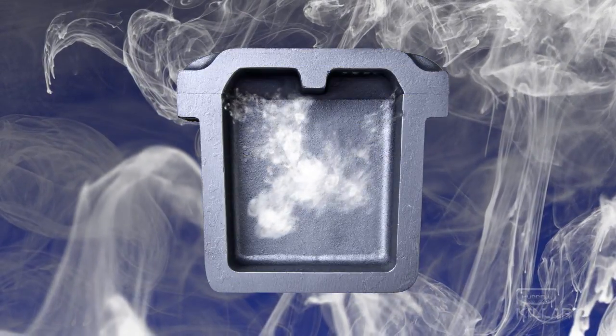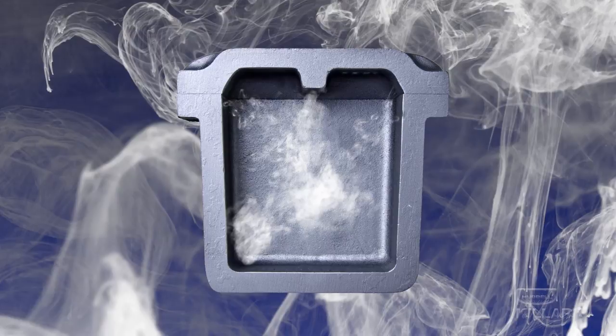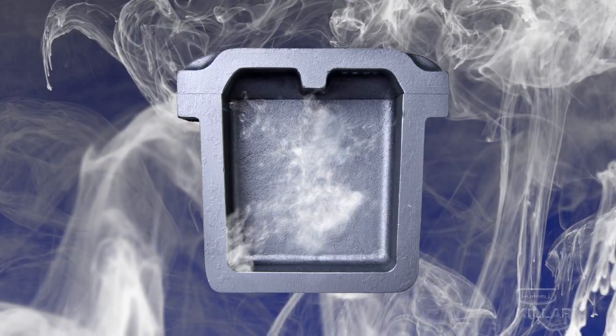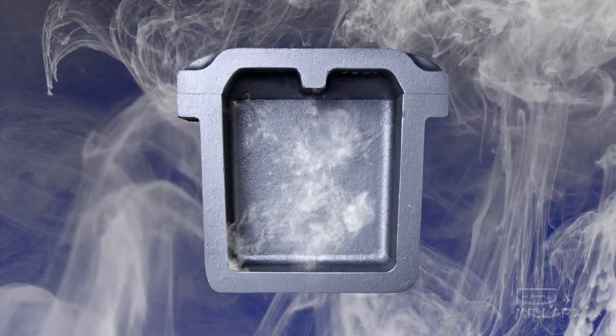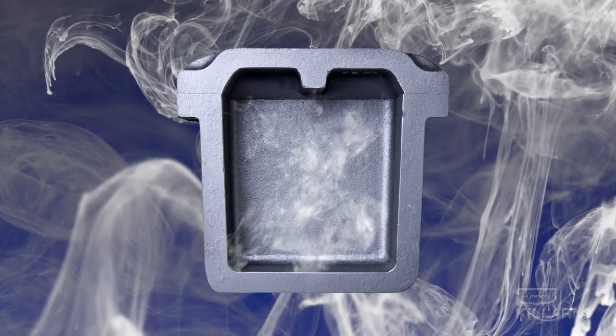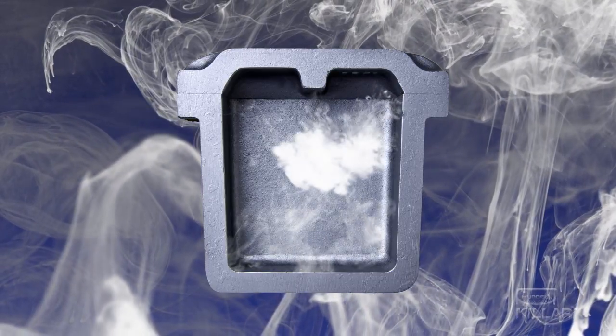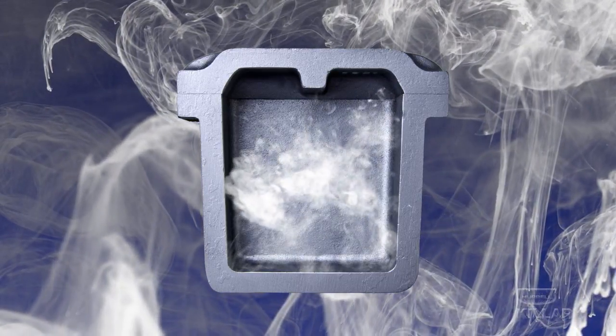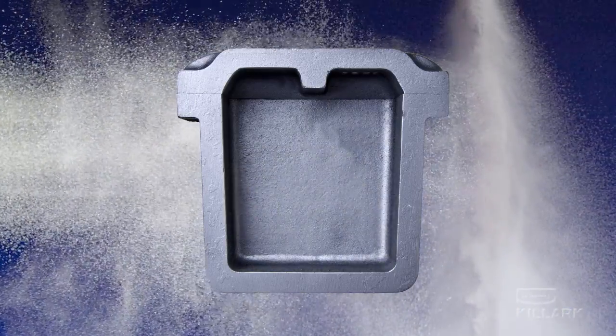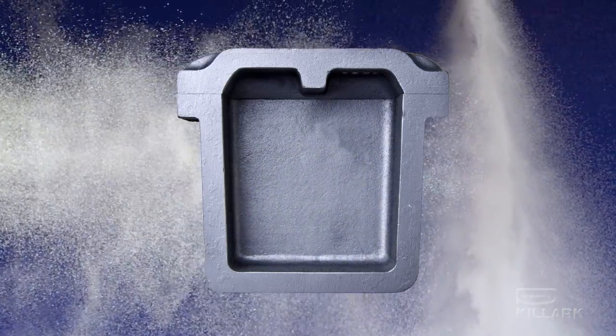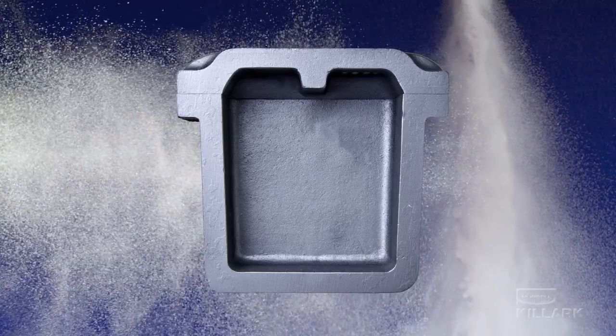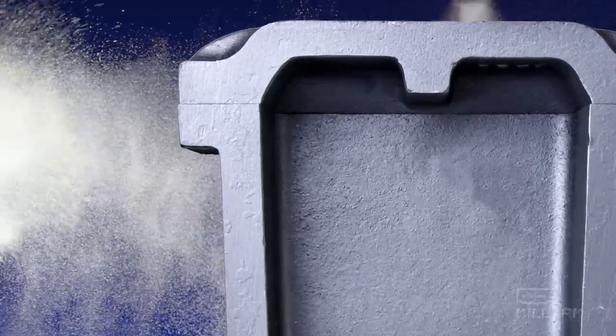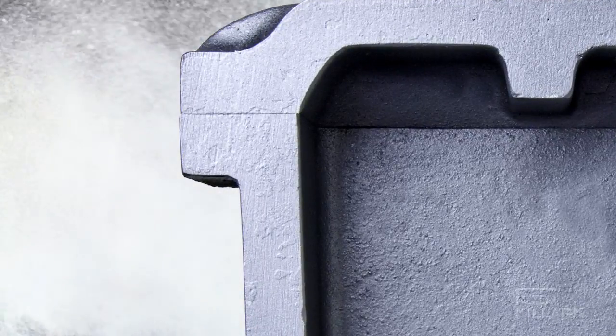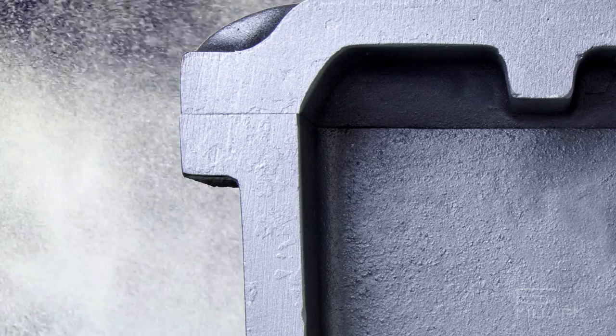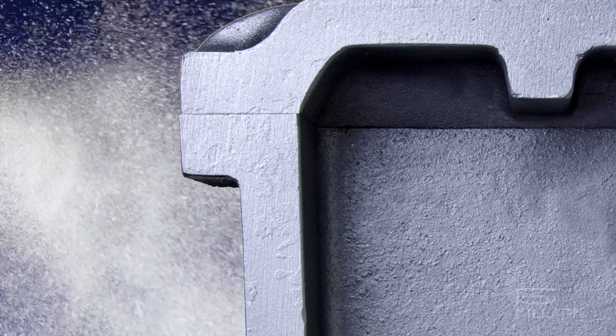The fluidity and compressibility of free gases and vapors will permit their inevitable migration and seepage into spaces and equipment unless very specific and robust design measures are taken to prevent it. In contrast, the physical nature of dust permits a more inherent reliance on tightly assembled or firmly gasketed enclosures to seal dust away from electrical components.